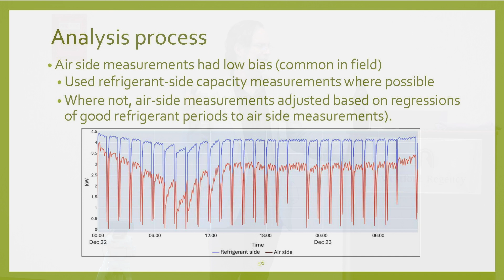On the measurement side, the blue trace is the refrigerant mass flow meters for a particular period of time of a few hours, and the red is the air side measurements. On the cooling measurements, the air side were consistently low by between 10 and 20%. And we're not really sure exactly why, but it's probably the delay time of the humidity sensors. It's really hard to get accurate humidity sensors that are also fast. And when you're measuring stuff dynamically, that matters.